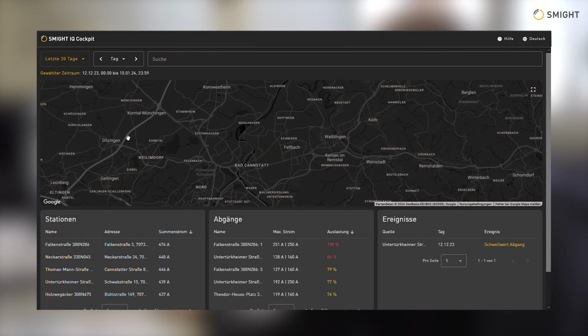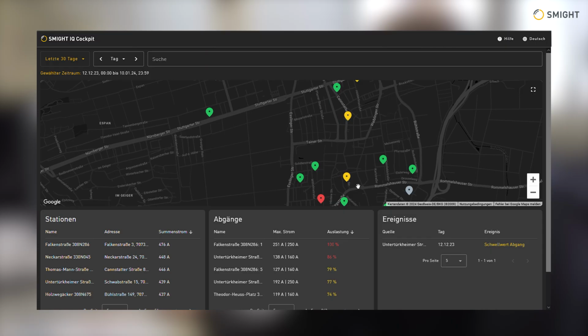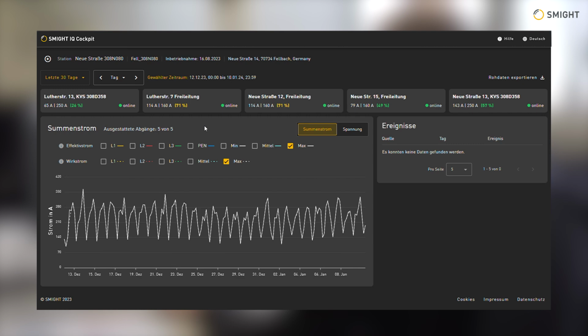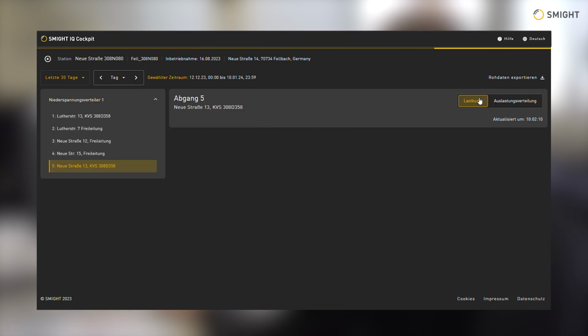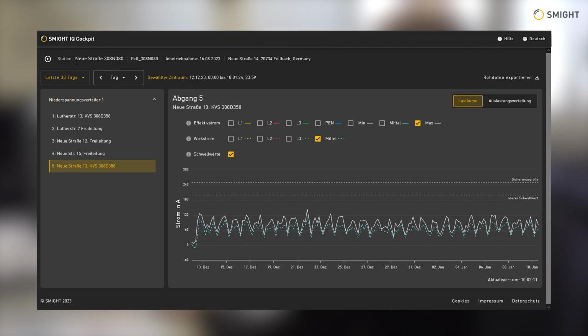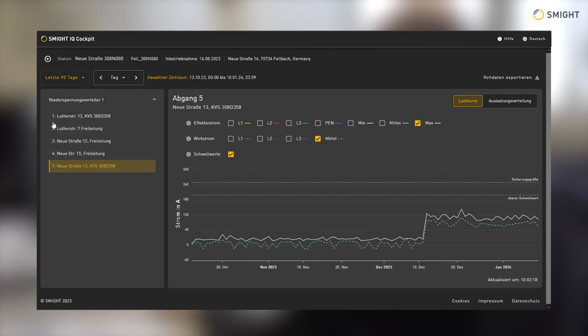We now go to the neighboring substation, the Neue Strasse substation. We display the outgoing circuits here and take a look at the Neue Strasse 13 feeder. We select the last 90 days and see that the circuit only has a low load, because this was a cable end with only a few connections on it. Then, in December, we transferred the load from the Bubengarten circuit to this circuit.